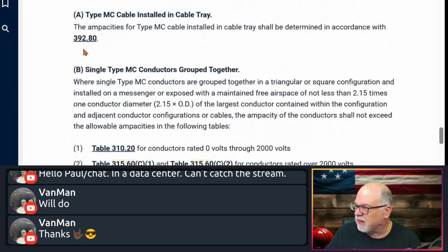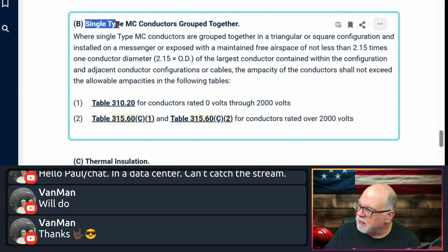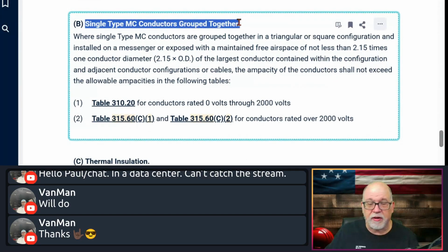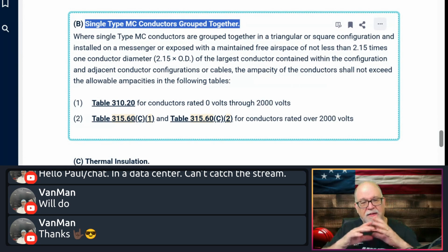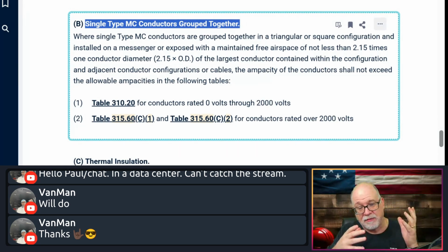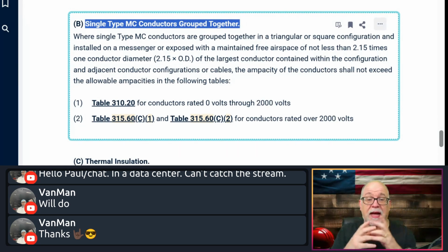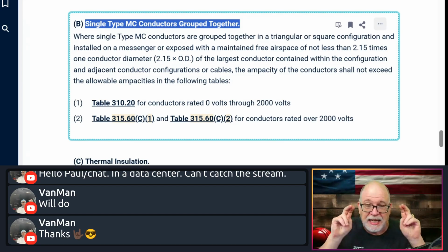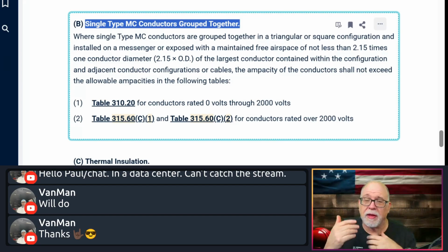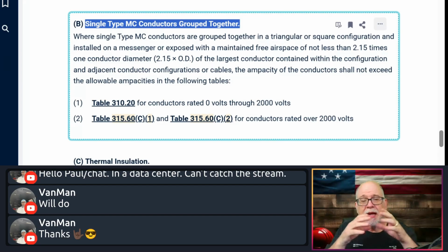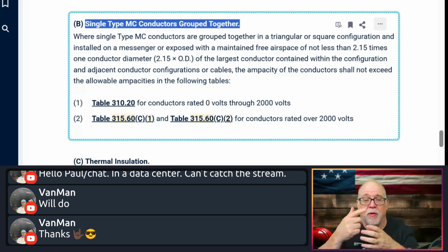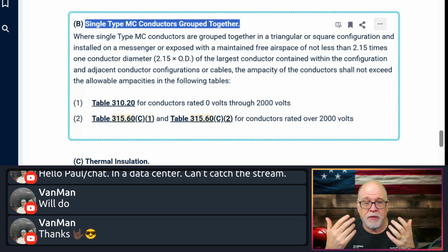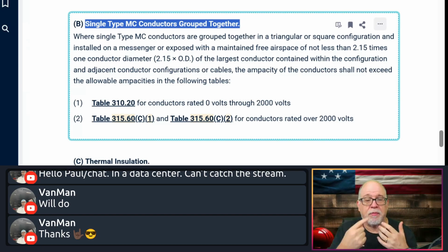So that's ampacity. Single type MC conductors grouped together. So this is maybe if you're using the ones with a single conductor in it, very rare, but in case you have it, and if you're not familiar with that, it's a single conductor with armor, and they're treated like an MI, a single conductor MI, although they make MI with multiple conductors. Basically bringing them all together. So if you had 3 hots and a neutral or whatever and an equipment ground, they would be separate. And you just make sure they all stay close together, right?